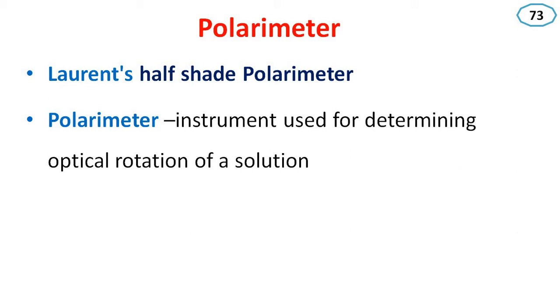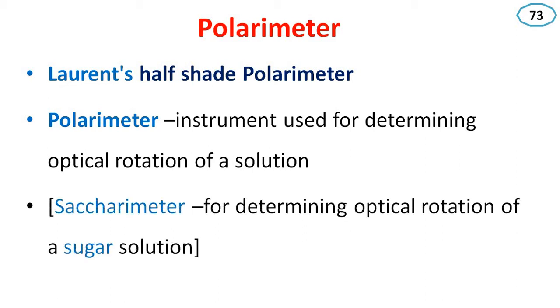Optical rotation we have already discussed. The polarimeter is a measuring instrument used for solutions — that may be a sugar solution, that may be a salt solution, etc. When used specifically for sugar solutions, the instrument is called a saccharimeter. A saccharimeter is used for determining optical rotation of a sugar solution.